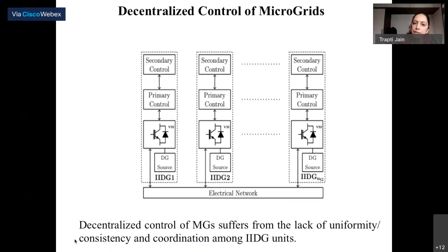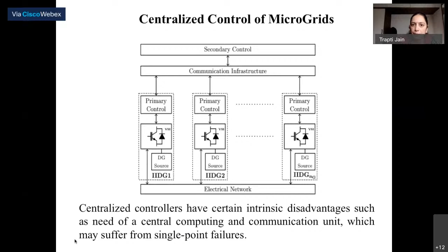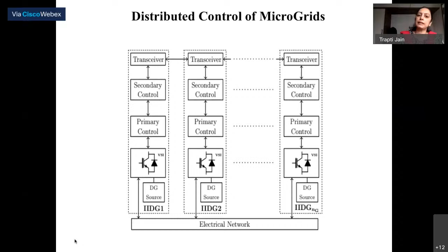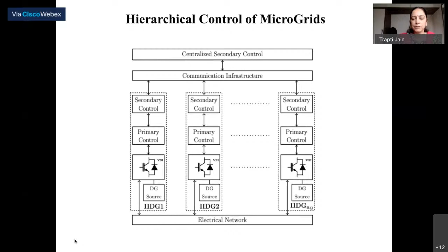Then we have centralized control of microgrids, but it requires a good communication infrastructure because there is only one control which coordinates with the different IIDG units. It receives information from the primary control of all the available IIDG units and then informs them of the controls. Then we have distributed control of microgrids. It is an addition to the decentralized controller: the secondary control units, which earlier were not able to know the conditions of the other IIDG units, now receive information about the other IIDG units also. Then we have hierarchical control of microgrids, which requires both secondary control as well as centralized control. So if any one control fails, the other one is there to take care of things. So these kinds of control structures are there.